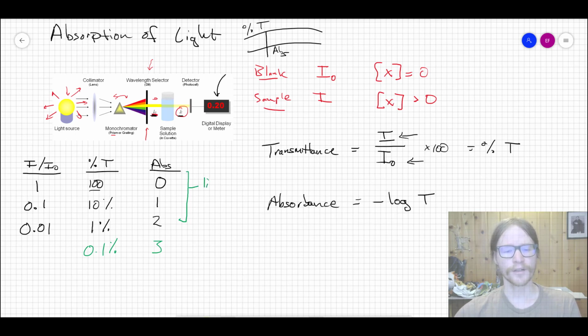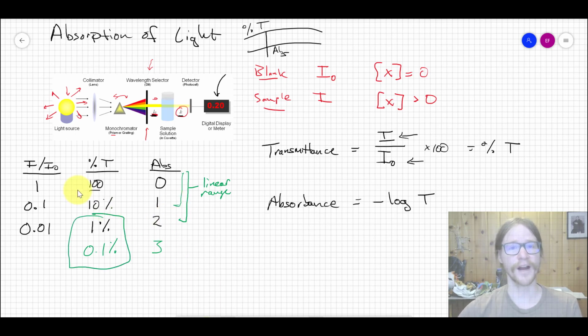So we often call the linear range of absorbance measured in a spectrophotometer, typically 0 to 2, maybe 2.5, and then in some high-end research spectrometers up to 3. For cheap spectrometers, sometimes that absorbance range is linear only up to 1, especially at the bounds of the UV and the visible spectrum. This is because you're absorbing such a small fraction, or actually transmitting such a small fraction, which is the signal you're measuring.